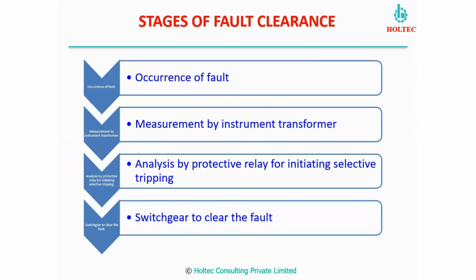Thank you. Analyze of the protective relay for initiating a selective tripping. Selective tripping is a very important aspect in any protection system. This we will discuss later in the slides. And when this relay will check and initiate a selective tripping, a switchgear will trip, which will clear the faulty sections or faulty equipment. So in that way, these are the various stages.